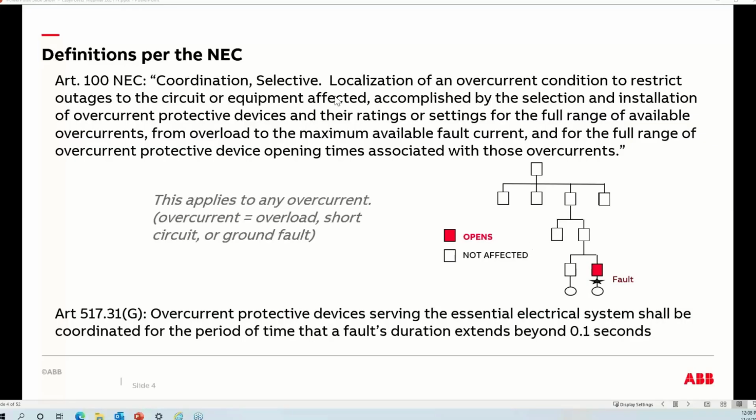That kind of visually, when you're reading it, perhaps distinguishes it quickly from 0.1 second requirements. Realize that 0.01 second coordination is, again, I feel, an industry adopted term. It's used widely in specifications, but it's technically not correct. It almost sounds like it's to the exclusion of coordination between 0 and 0.1 seconds, and that's not the intent. It's just, again, an industry adopted term to indicate the application of this definition.